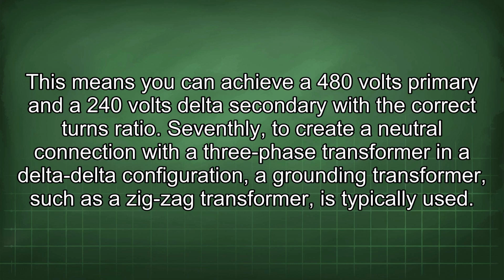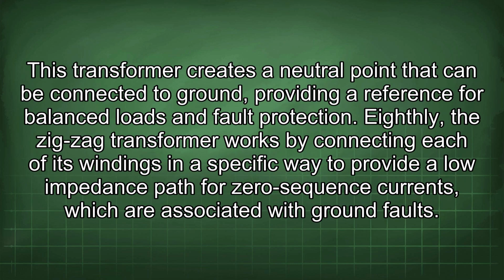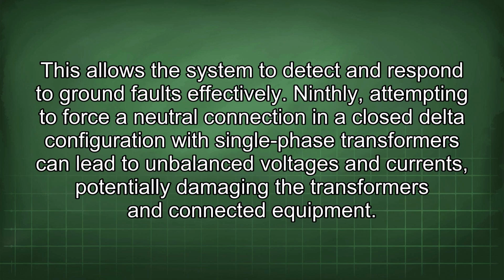Seventhly, to create a neutral connection with a three-phase transformer in a delta-delta configuration, a grounding transformer, such as a zigzag transformer, is typically used. This transformer creates a neutral point that can be connected to ground, providing a reference for balanced loads and fault protection. Eighthly, the zigzag transformer works by connecting each of its windings in a specific way to provide a low impedance path for zero-sequence currents, which are associated with ground faults. This allows the system to detect and respond to ground faults effectively.